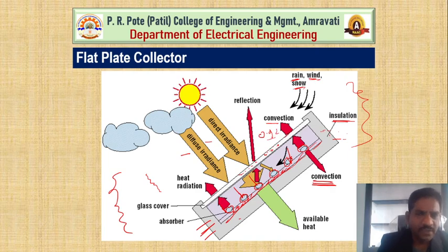And because of the reduced heat transfer rate, the collector efficiency of a flat plate collector also decreases. So to increase the efficiency of the flat plate collector, always clean this transparent cover every 1 week or 2 weeks or 1 month, always wash or clean this transparent cover. Whenever you remove the dust, the heat transfer rate improves and our collector efficiency also increases, guys.